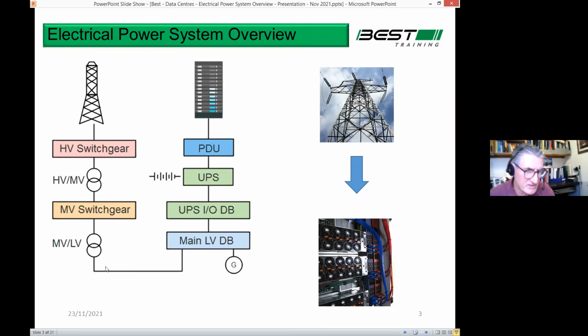Then when you get closer to the data centers, the buildings where the data is being processed, you have to transform back down, obviously, to a safer level of voltage, which is 400 volts. And we transform down through these MV/LV transformers and you supply into a main board here. So the transformer is usually quite close to the main board. And then you have a generator feeding in.